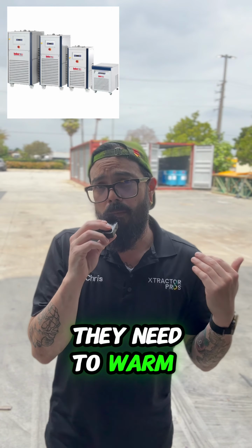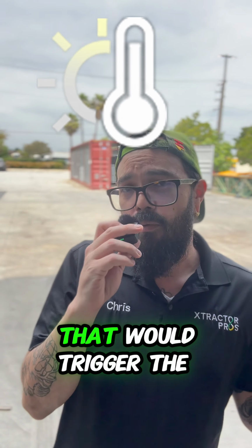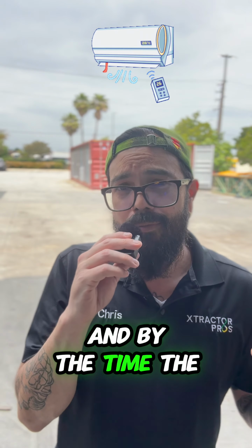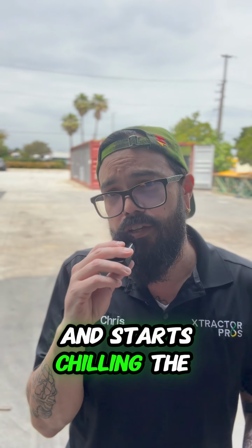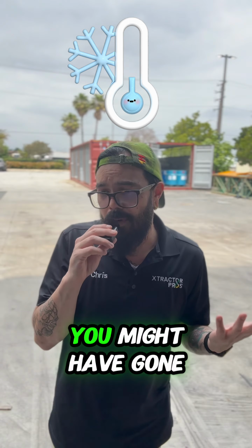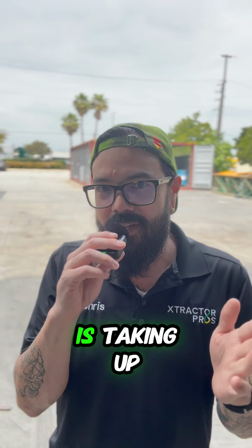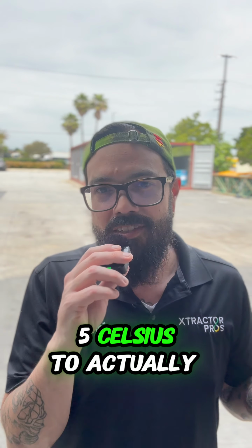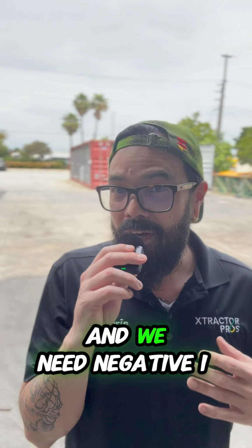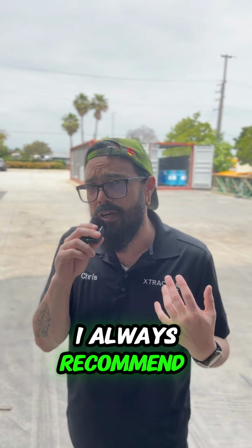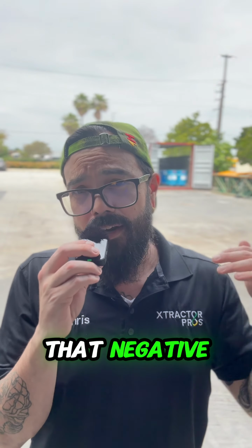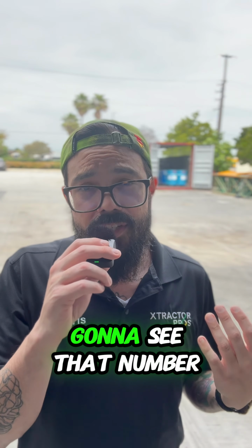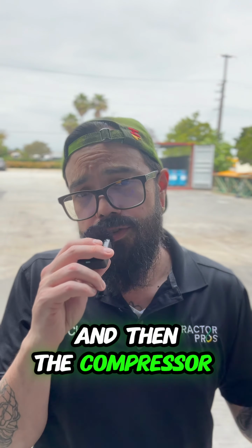Chillers need to warm up beyond your set temp, and that would trigger the compressor. And by the time the compressor actually kicks on and starts chilling the fluid again to bring it back down to temp, you might have gone above your condensing temperature. You might have got warmer than negative 1 just because the compressor is taking up until 5 Celsius to actually kick on, right? And we need negative 1 Celsius. I always recommend negative 10. A chiller will hold at negative 10, and once you start recovering, you're going to see that number budge to about negative 9, negative 8, and then the compressor usually kicks on.